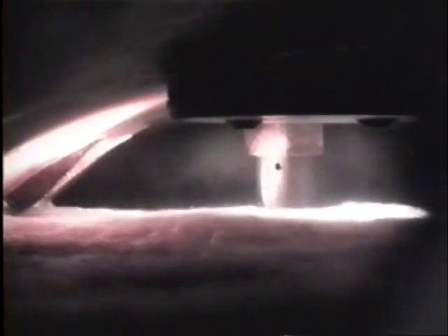the effect. Within a few seconds, the water level rises to the extent that water begins to be drawn into the steam takeoff. As soon as the high demand for steam moderates, the water level drops and the low water cutoff turns off the burner. A sustained high steam demand can result in the tripping of the low water and auxiliary low water cutoffs while that demand is still present.